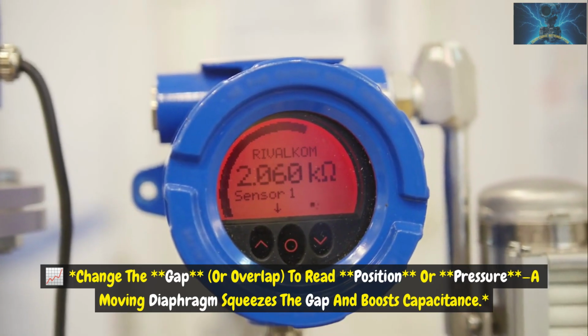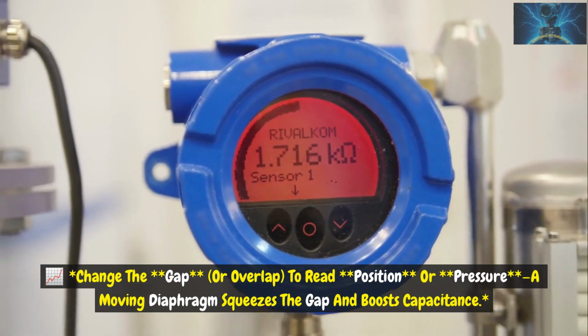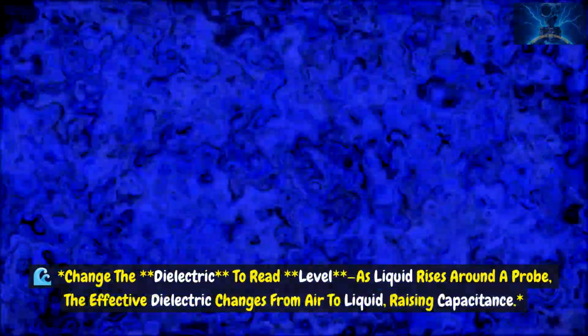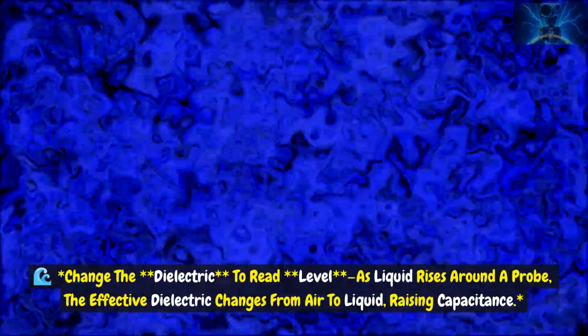A moving diaphragm squeezes the gap and boosts capacitance. Change the dielectric to read level. As liquid rises around a probe, the effective dielectric changes from air to liquid, raising capacitance.